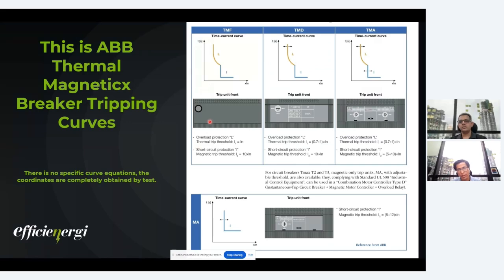Then this one is basically fixed time, where you cannot adjust the overload, and again you cannot adjust the magnetic tripping as well. So this is particularly a fixed kind of breaker. These breakers are normally used directly for the protection of the short circuit region.